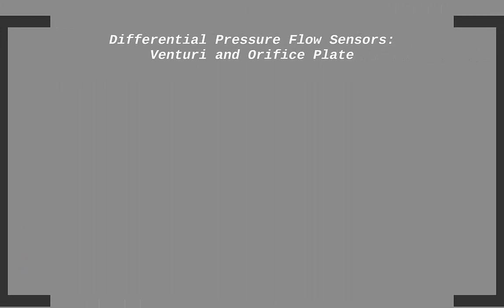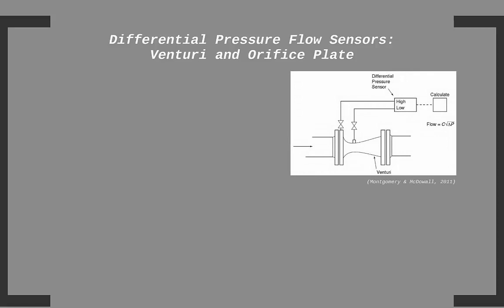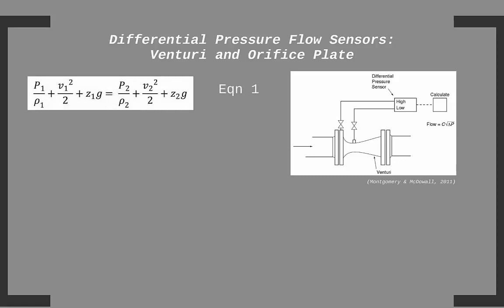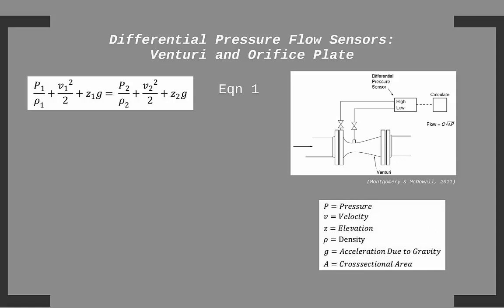Now let's talk about flow sensors. Many flow sensors, whether they are used to measure airflow or water flow, fall under the general category of differential pressure flow sensors. Basically, all such flow sensors work off the relationship defined by Bernoulli's equation. It is basically a conservation of energy equation. The total energy at state 1, upstream of the flow sensor, will equal the total energy at state 2, which could be somewhere downstream or in the middle of the sensor.